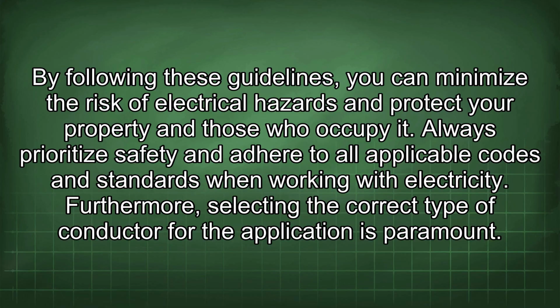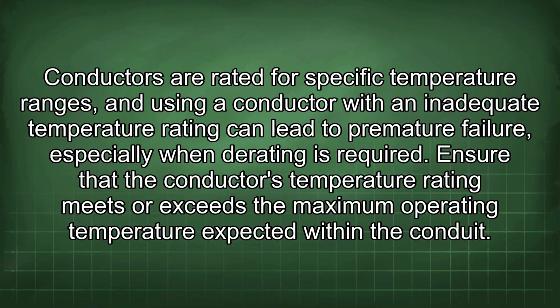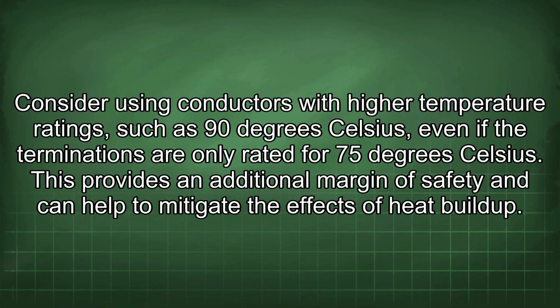Furthermore, selecting the correct type of conductor for the application is paramount. Conductors are rated for specific temperature ranges, and using a conductor with an inadequate temperature rating can lead to premature failure, especially when derating is required. Ensure that the conductor's temperature rating meets or exceeds the maximum operating temperature expected within the conduit. Consider using conductors with high temperature ratings, such as 90 degrees Celsius, even if the terminations are only rated for 75 degrees Celsius. This provides an additional margin of safety and can help to mitigate the effects of heat buildup.